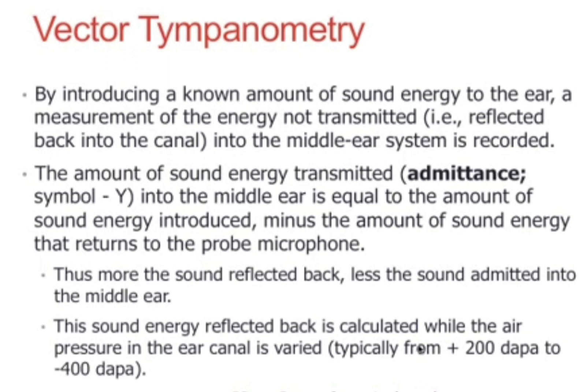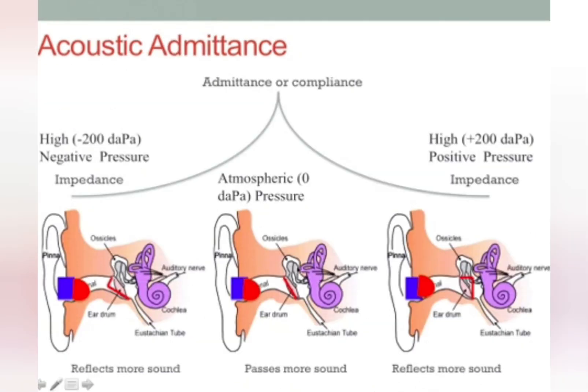We can know the amount of energy that is admitted and reflected back by changing the pressure in the ear canal. The pressure is altered from 200 daPa to negative 400 daPa, and that changes the compliance of the tympanic membrane. The admittance of sound is maximum when the pressure inside the middle ear and in the ear canal is the same — that is at atmospheric pressure or 0 daPa.